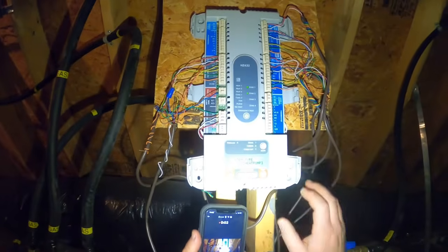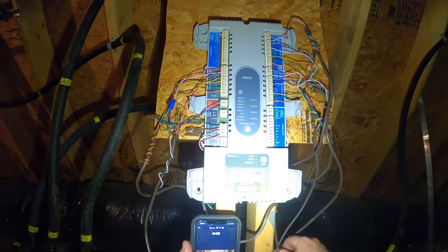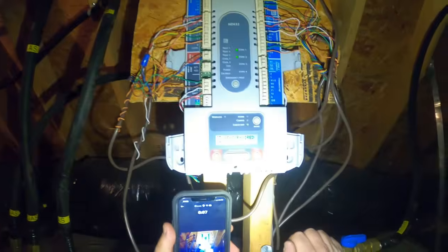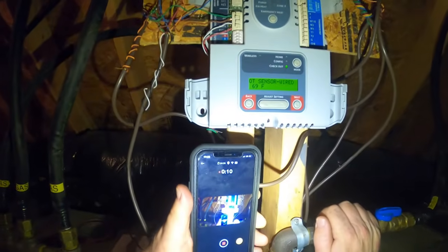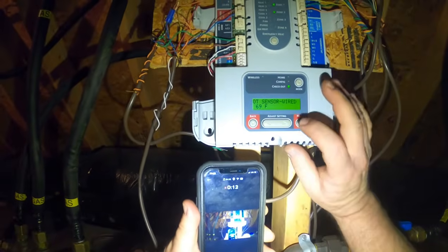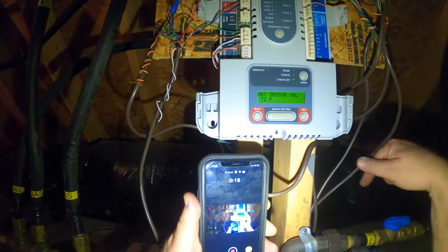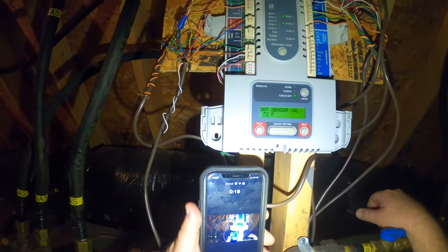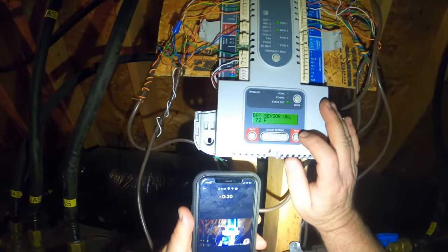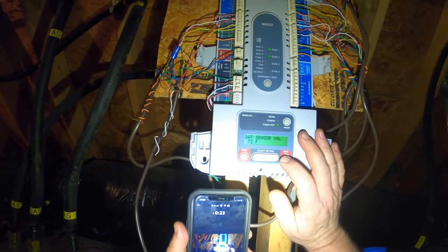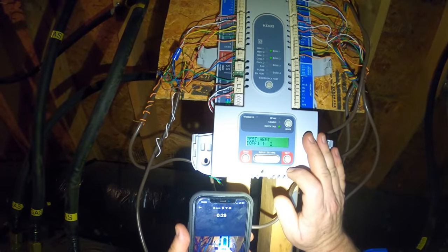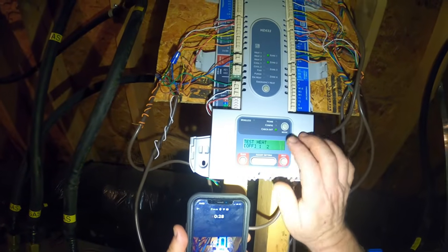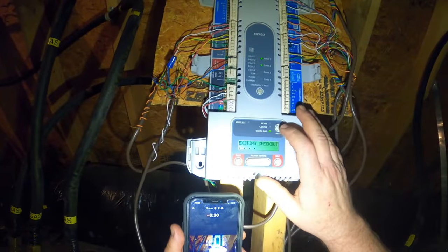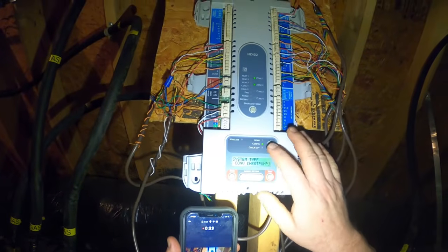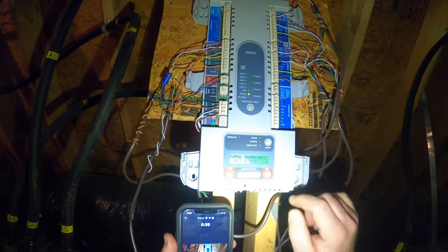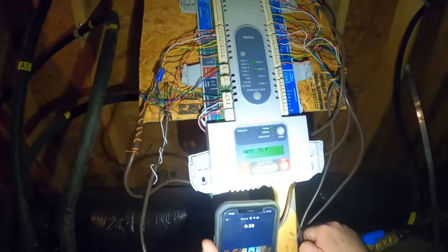So right here now we're going to go through our checkout operations. It's telling me our outdoor temperature sensor there is reading 69 degrees. Tells me our DAT sensor on our supply plenum is reading 72 degrees, which is about what it is inside the house. You hear the blower running. So now we're going to test heat 1. Let's go back and cancel our purge real quick. Let that blower shut off.